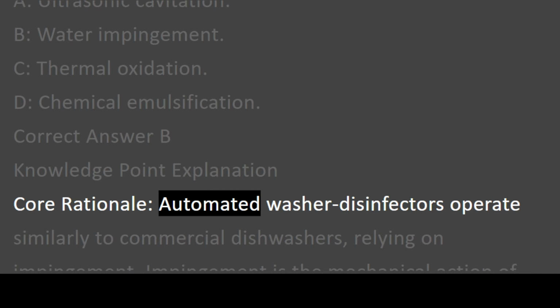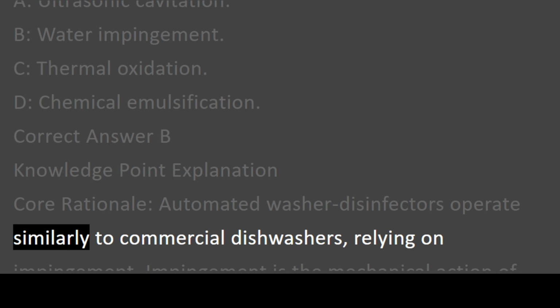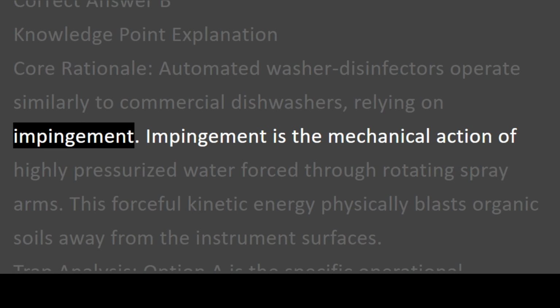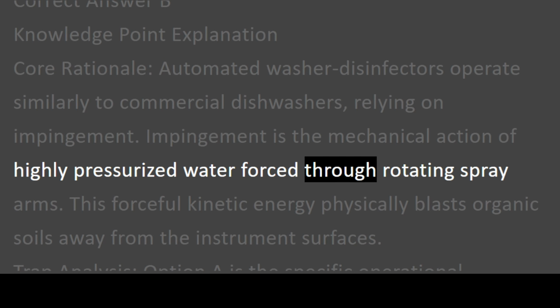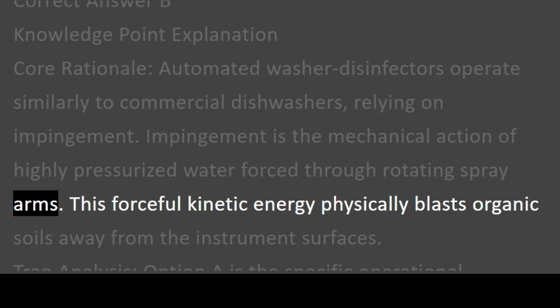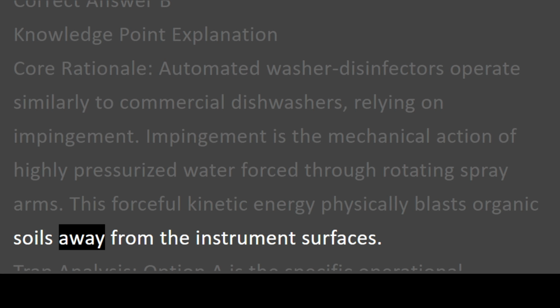Core rationale. Automated washer disinfectors operate similarly to commercial dishwashers, relying on impingement. Impingement is the mechanical action of highly pressurized water forced through rotating spray arms. This forceful kinetic energy physically blasts organic soils away from the instrument surfaces.